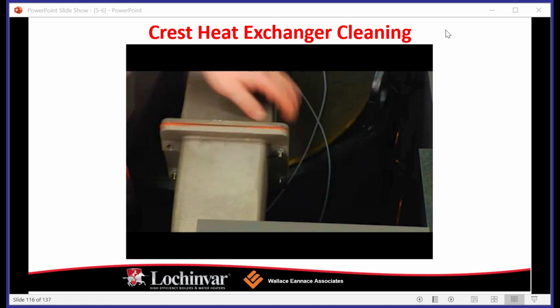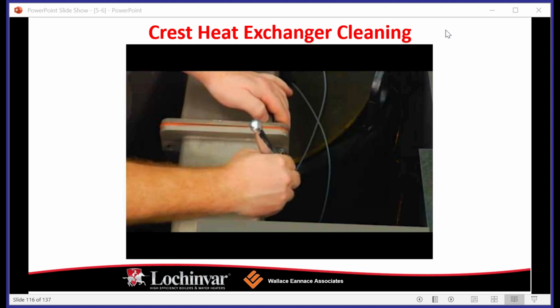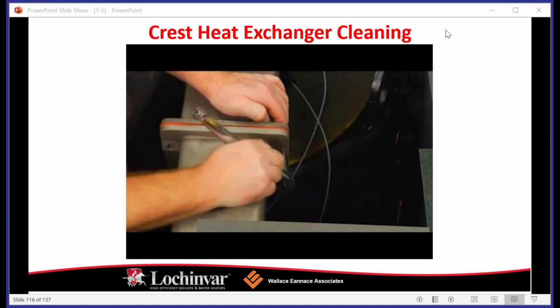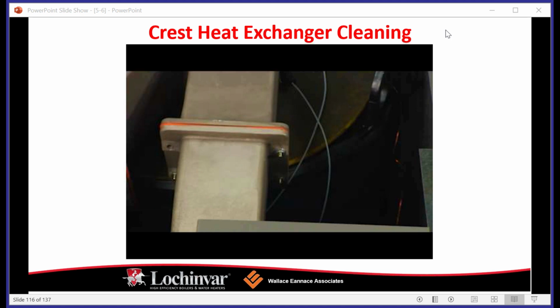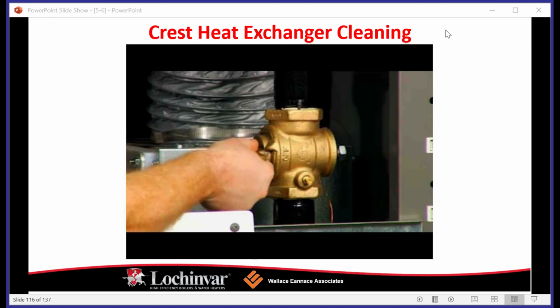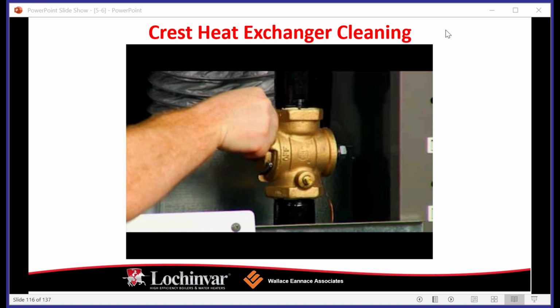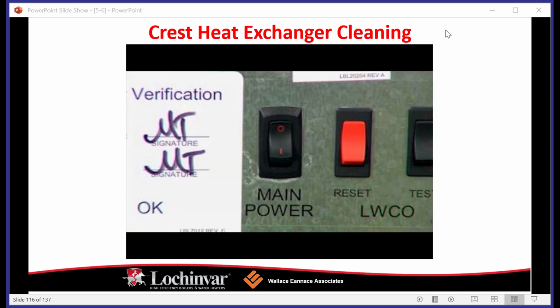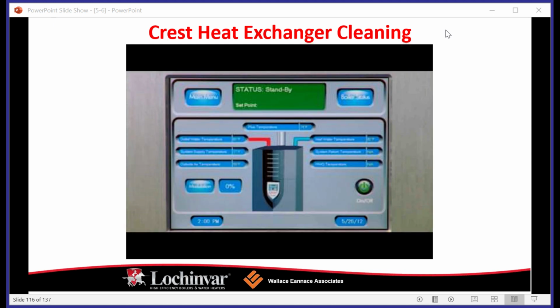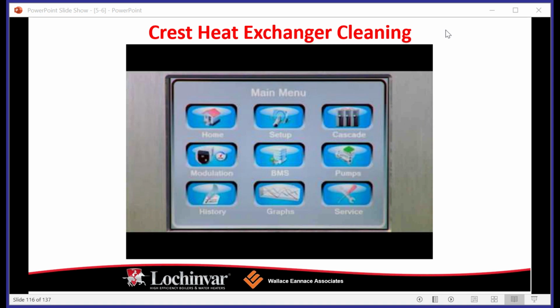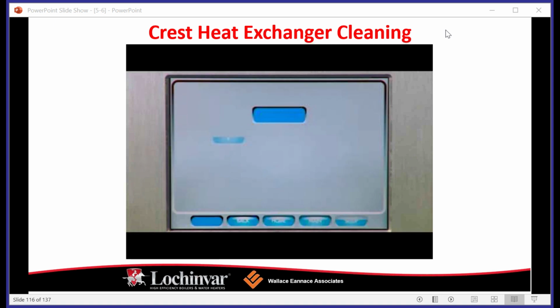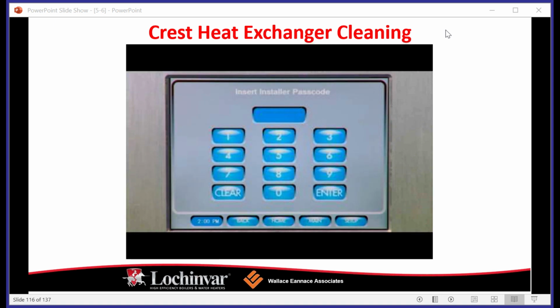A gasket is used to seal between the burner and the heat exchanger door. Care must be taken not to tear or damage the gasket. If the gasket is damaged or torn, then it must be replaced. Remove the wiring from the igniter and flame rods. Remove the insulation blanket from the top of the heat exchanger. Remove the nuts and washers securing the heat exchanger door to the heat exchanger. Pull the heat exchanger door up and away from the boiler. Use caution when removing the heat exchanger door to prevent damage to the refractory mounted on the inside.